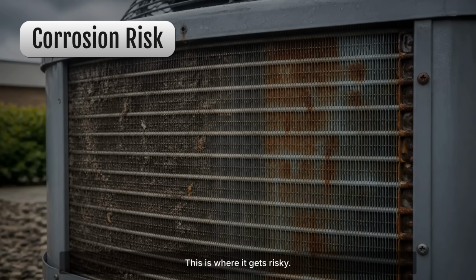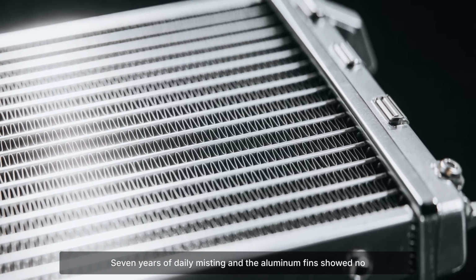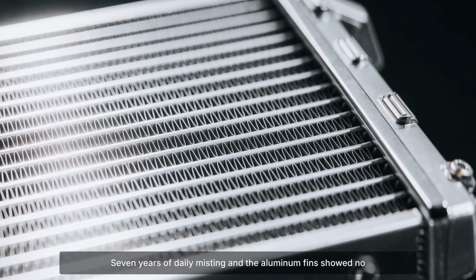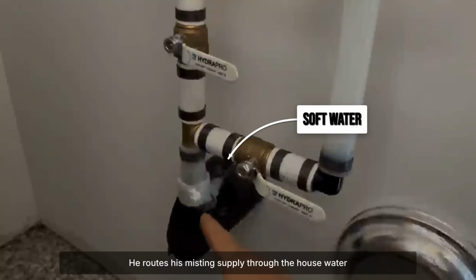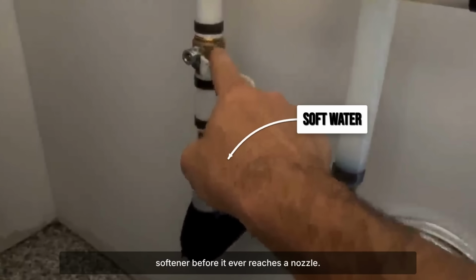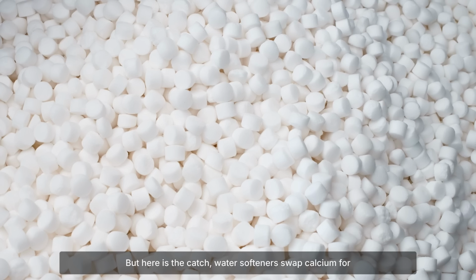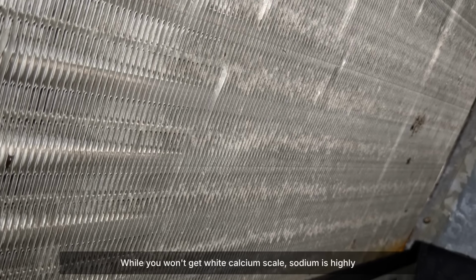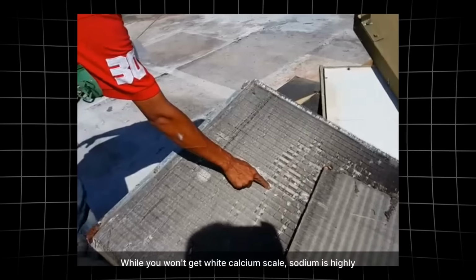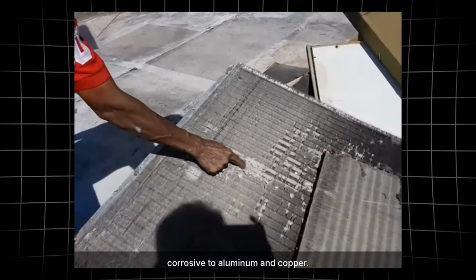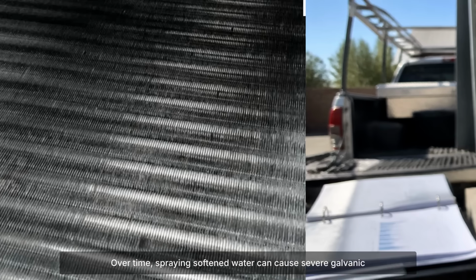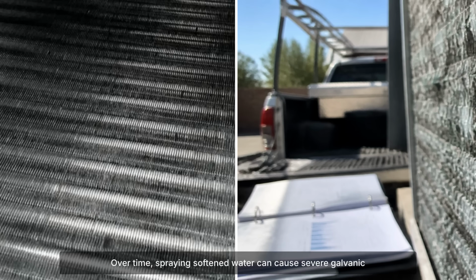Then he showed me the coils. This is where it gets risky. 7 years of daily misting and the aluminum fins showed no mineral scaling. He routes his misting supply through the house water softener before it ever reaches a nozzle. But here is the catch. Water softeners swap calcium for sodium. While you won't get white calcium scale, sodium is highly corrosive to aluminum and copper. Over time, spraying softened water can cause severe galvanic corrosion, eating away your condenser coils from the outside in.